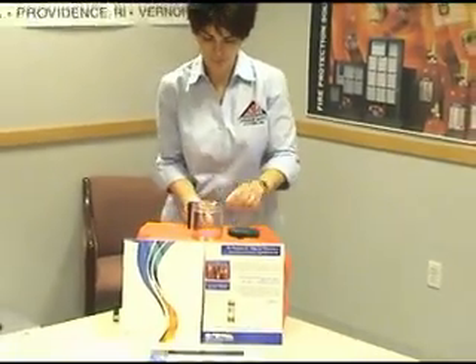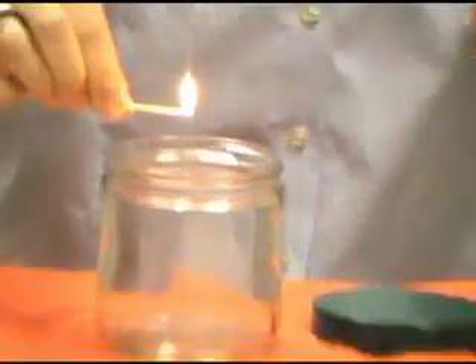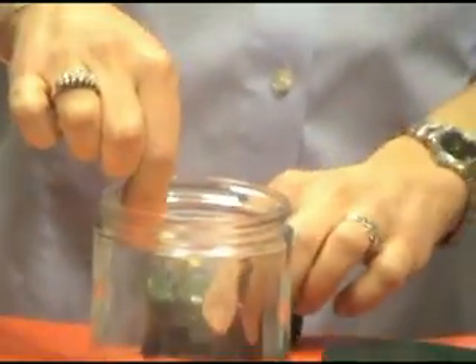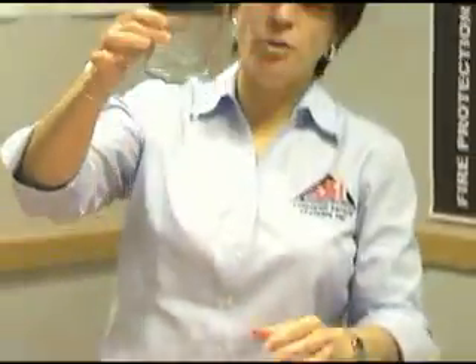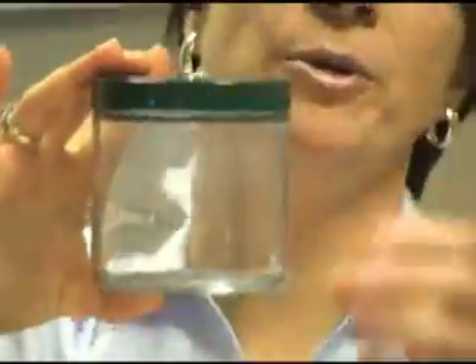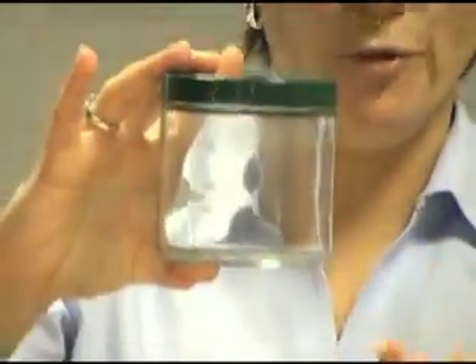Now if I light this match, you'll see that the flame is extinguished within the vapor space. I didn't have to dip it into the liquid. Now if I showed this to you — you may not be able to see it on the camera — but you can see the smoke stratifying within the vapor space, showing you that there's a vapor in here of the Novec 1230.